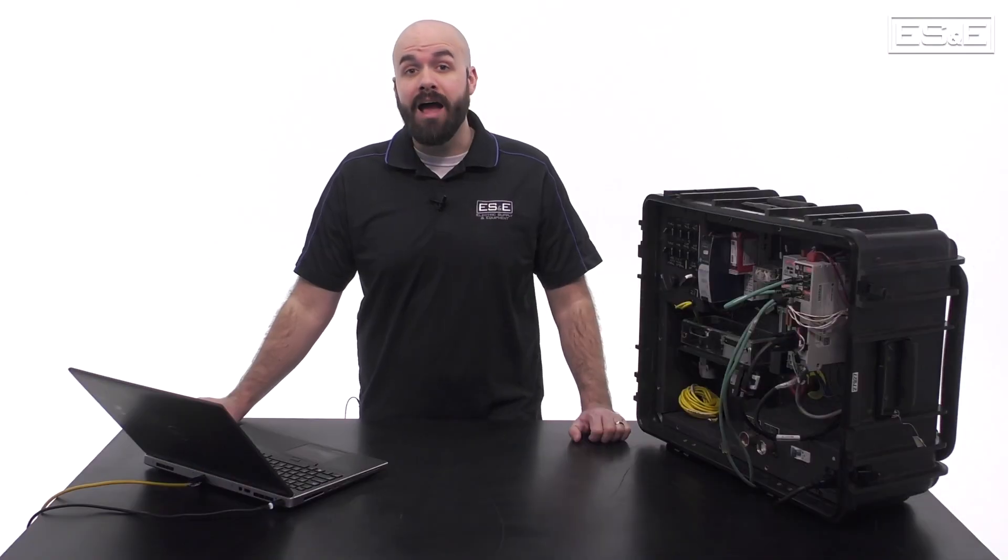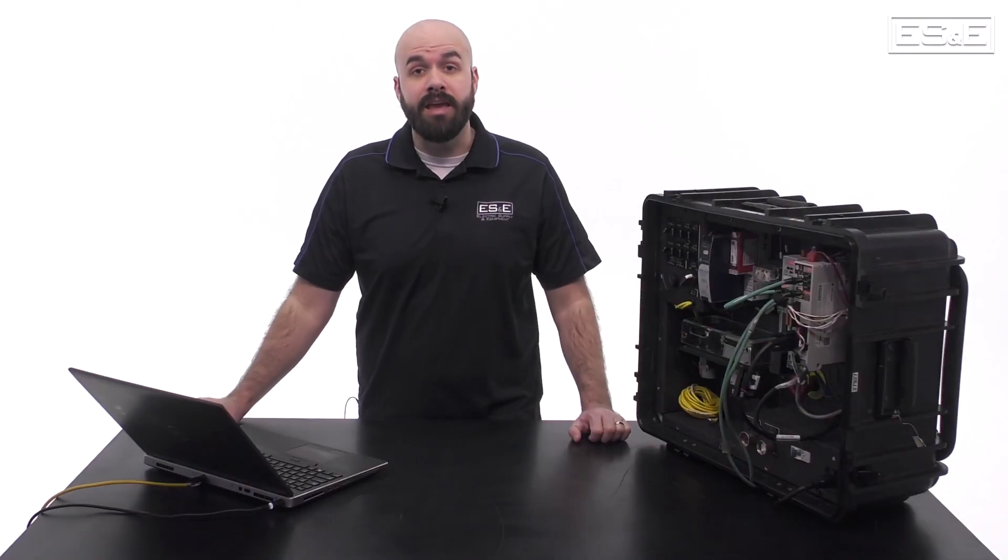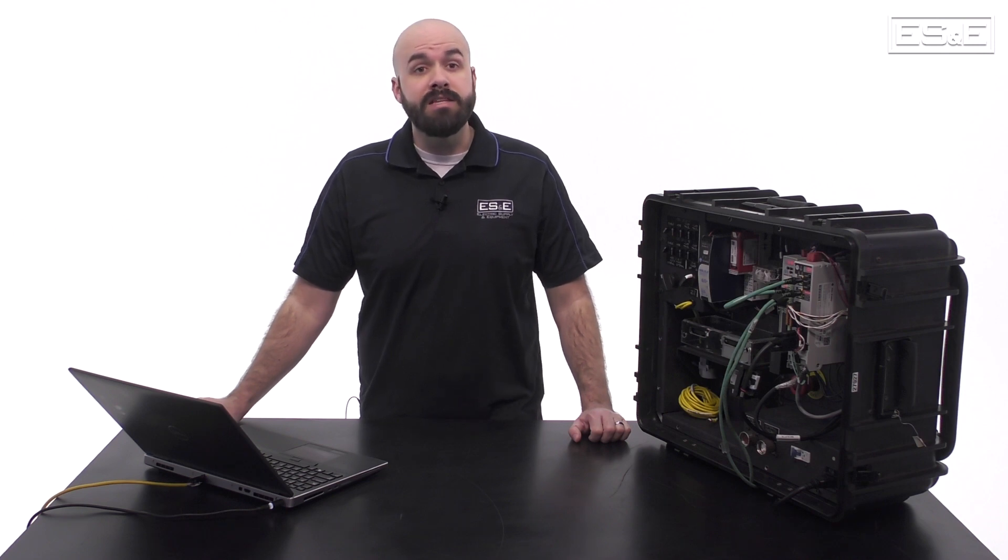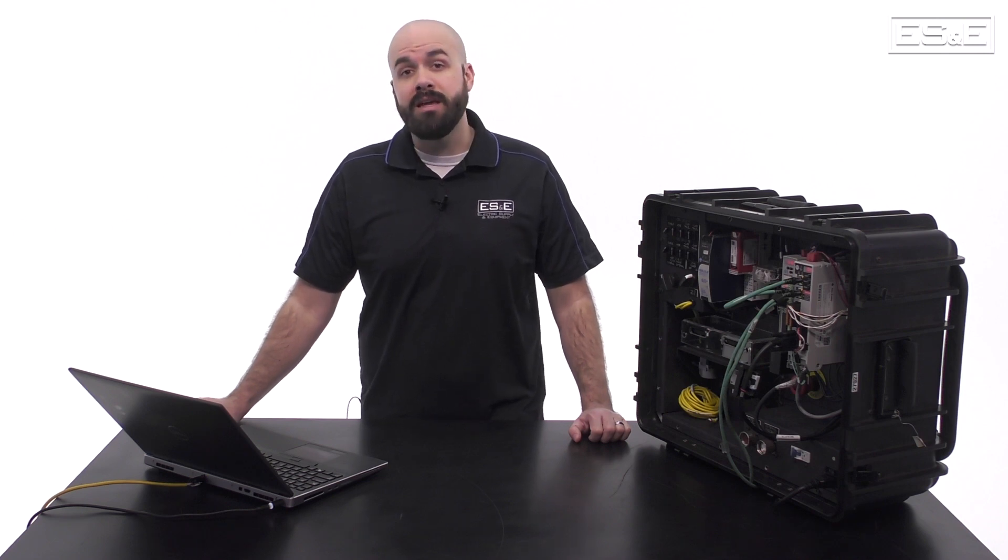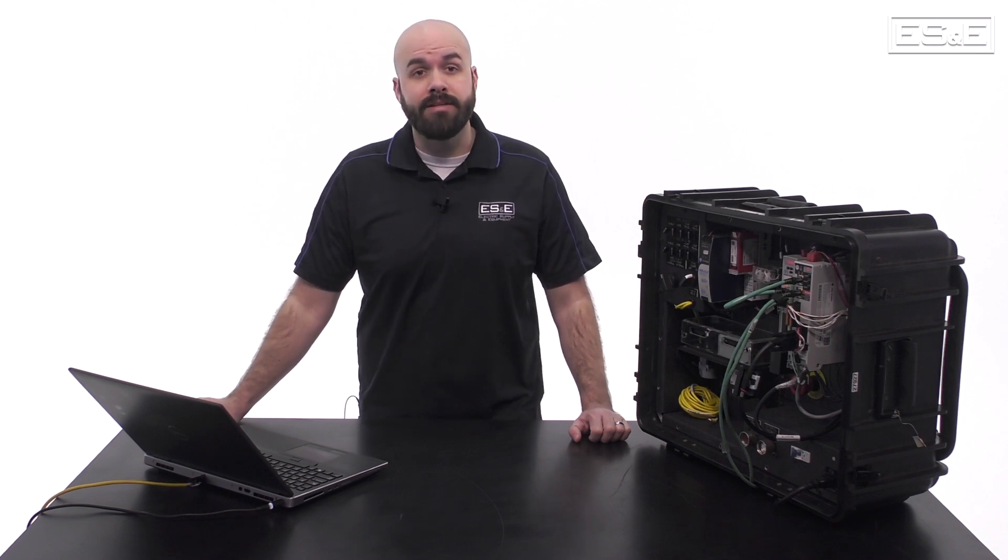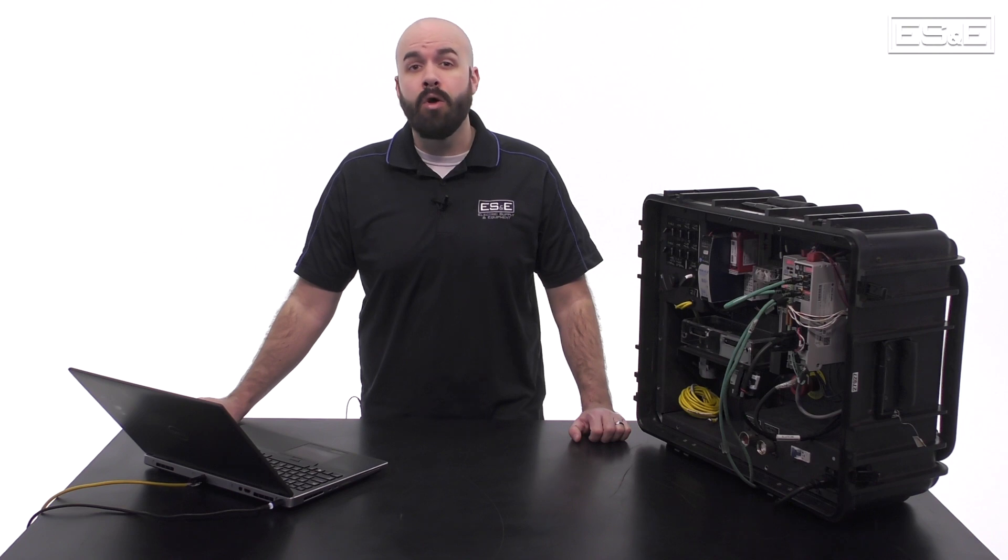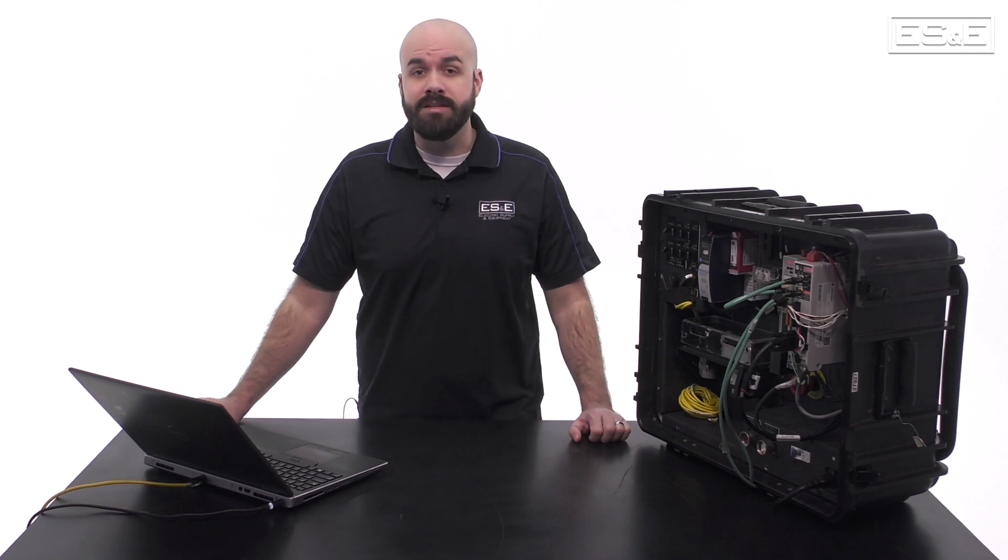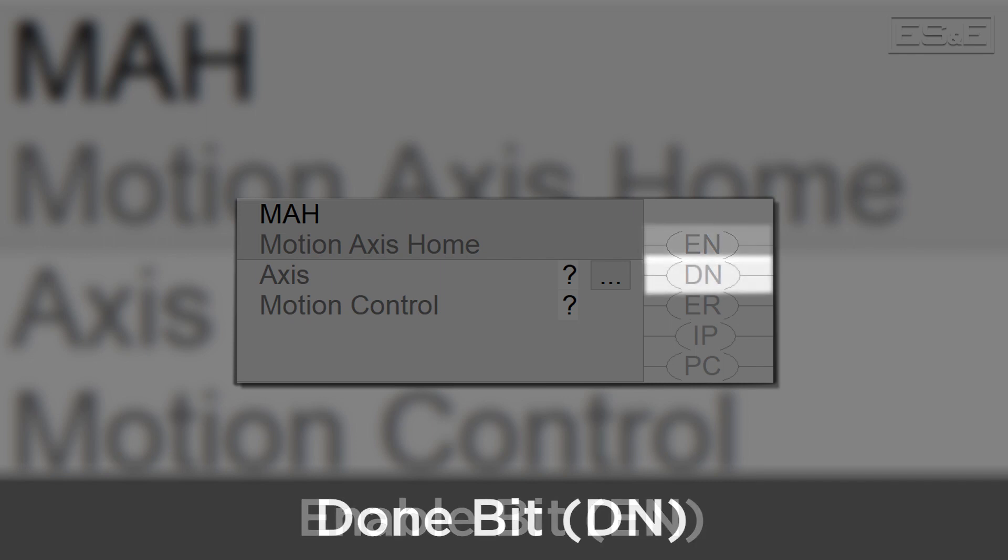Then there are five status indicator bits. None of these bits tell you anything about the current state of the target axis. They are only diagnostics associated with the given instruction. The EN, or enable bit, will be true when the rung that the instruction is on goes true. The DN, or done bit, will be true when the Motion instruction executes successfully with no errors. The state of the done bit only updates when the enable bit transitions from false to true.